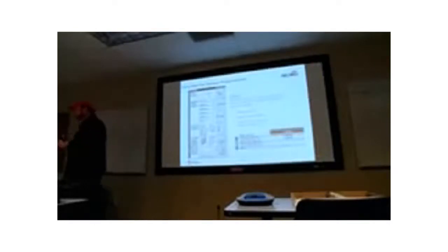Why do I mention this? Because if you're looking at your system, you're saying, okay, I'm going to have to guess. Which one do I think it is? Which factors should I use? I would say if somebody puts a gun to your head, I would use the factors in the middle column, the medium pressure ones, because that's going to cover you. If you have openings in existing air handling units, almost all of those are medium pressure. That is, they're set for about 1,200 to 1,400 feet per minute. If you do the calculations on the velocity that typically goes through them, it's probably around 1,400 feet. Okay. All right, let's get back. And then high pressure, you might get a particular case on that, but it's not really as common.